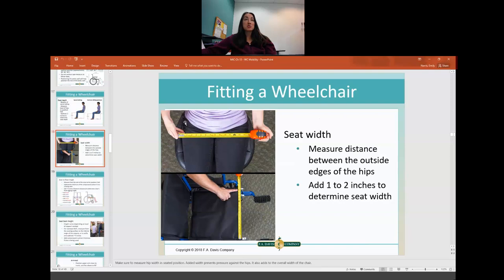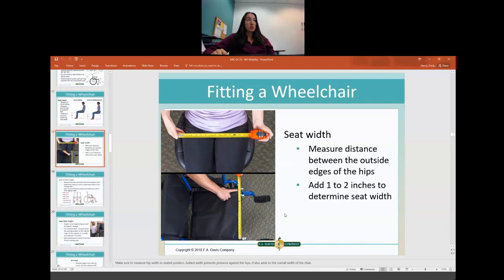For seat width, you measure the outer edges of the hips from one side to the other and add 1 to 2 inches. If the chair is too wide, it won't fit through doorways. If it's too narrow, it will put pressure on the patient's hips and could create a sore. You want it wide enough that it's not touching them on both sides, but narrow enough to fit through necessary spaces.